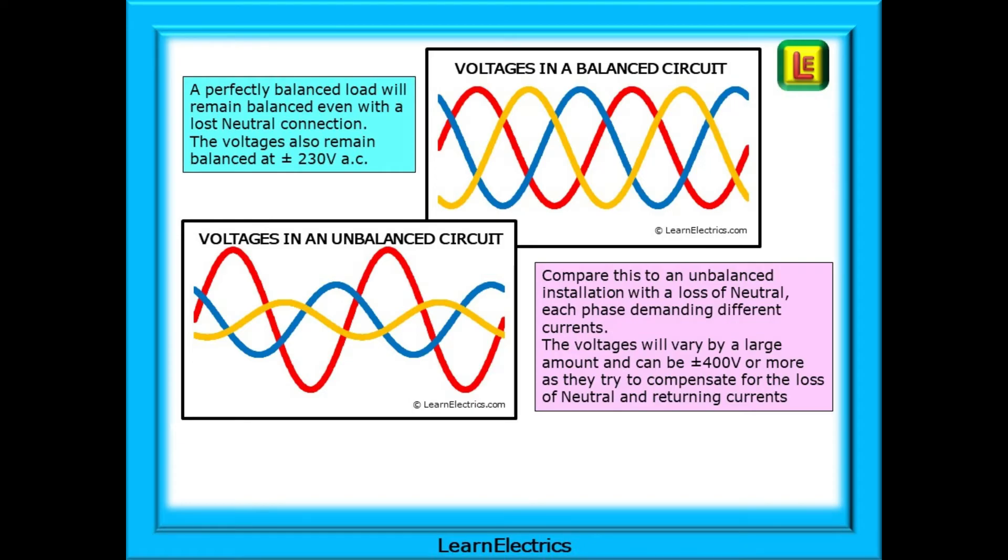A motor circuit might be a typical example as displayed on the top chart. Let us compare this to an unbalanced installation with a loss of neutral, where each phase is demanding different currents because the loads on each phase are all different. One phase might be feeding the lights, another phase will supply power to the kitchen ovens, and the third phase is fed to the offices. With a loss of neutral, the voltages can vary by significant amounts as shown on the lower chart.